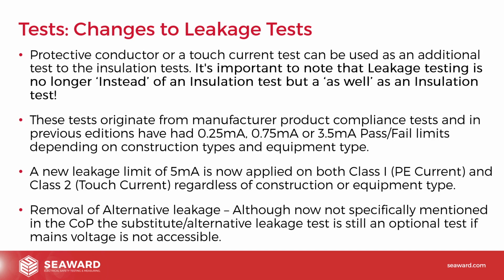What we've done with our products is make changes to the new 5th edition range of Seaward testers, which allow them to test all the way up to 5 milliamps for both PE current and touch current. So when we talk about testers being 5th edition compliant, that's really what we're talking about. We've made that change, so they will now measure all the way up to 5 milliamps for both PE current and touch current.